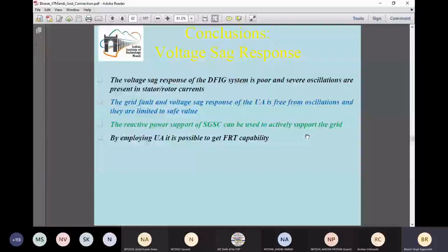By utilizing the chopper and the crowbars, it will be able to meet the severe grid connection requirements proposed in different countries and different electric grid codes. By utilizing the functionality available with the rotor side converter and stator side converter, it is possible to meet the strictest grid connection requirement for reactive power supply also.